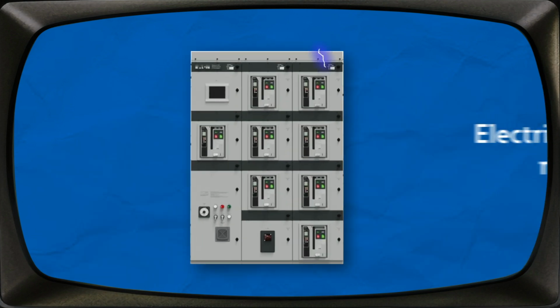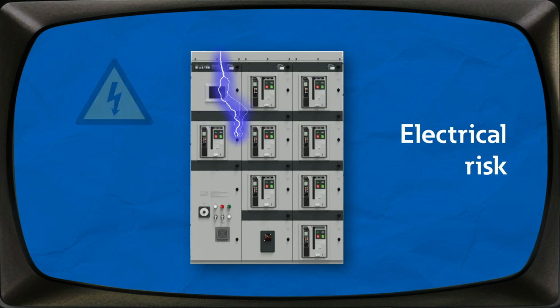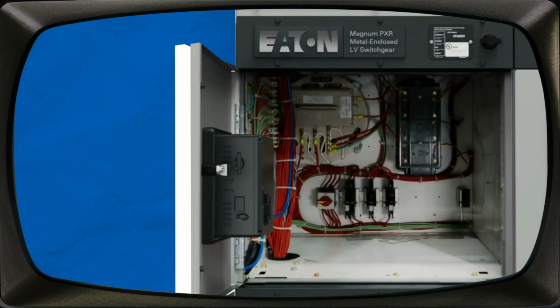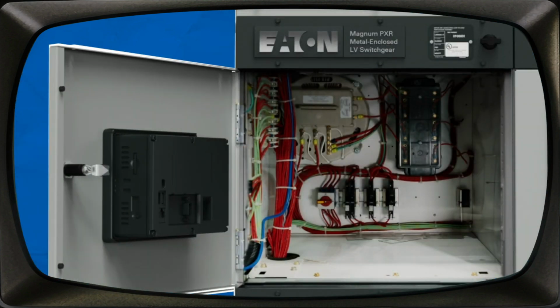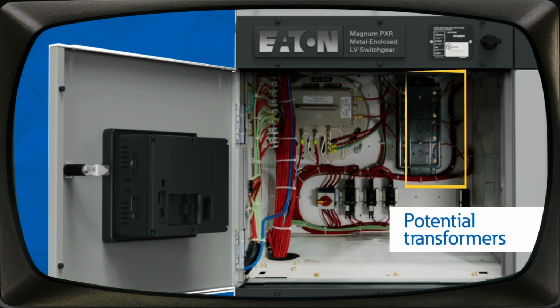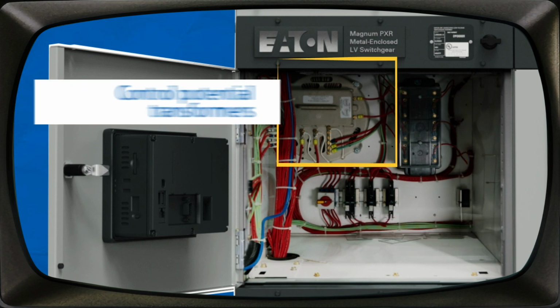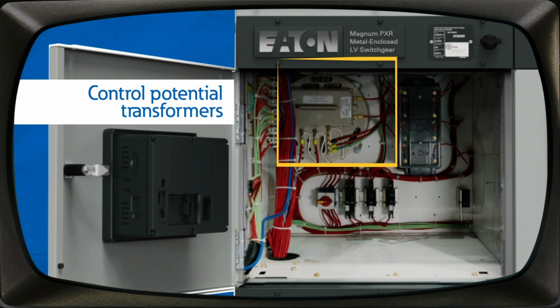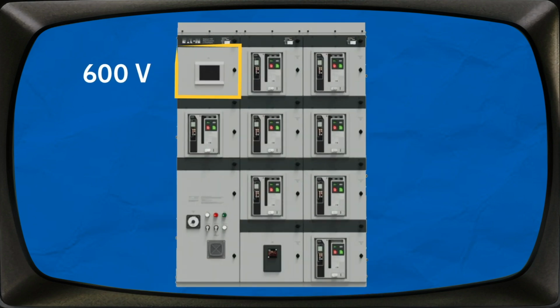This compartment usually presents the largest electrical risk to someone performing maintenance on the breaker section of switchgear. This is due to the instrument compartment containing potential transformers and control potential transformers that have the rated voltage of the switchgear connected to them. If the switchgear has 600 volts in the back, it will have 600 volts in the instrument compartment.